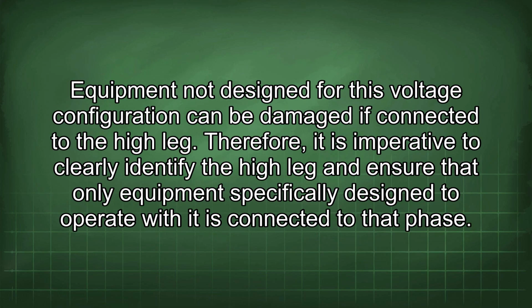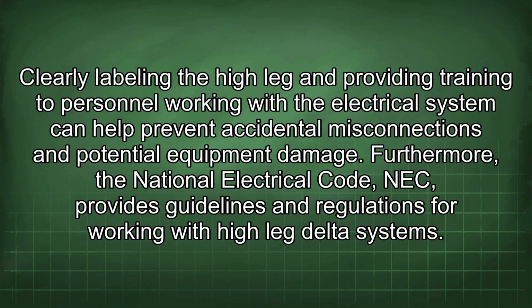Equipment not designed for this voltage configuration can be damaged if connected to the high leg. Therefore, it is imperative to clearly identify the high leg and ensure that only equipment specifically designed to operate with it is connected to the phase.